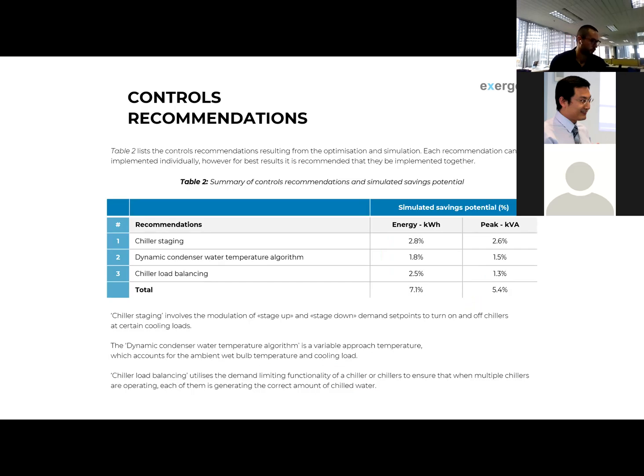And as a bit of a breakdown of where that's coming from, the model spat out 3 recommendations in this case, and each of those has an energy and a peak demand associated with it in terms of the savings potential. When we're running it through our simulation, it's shown that, for example, updating chiller staging has slightly under 3% potential efficiency improvement. But all 3 of those recommendations together, the chiller staging, the dynamic condenser water temperature algorithm, and the chiller load balancing, finish up at about a 7% direct energy reduction and just over 5% peak demand potential reduction.